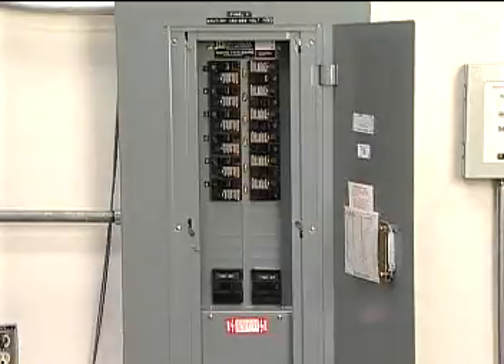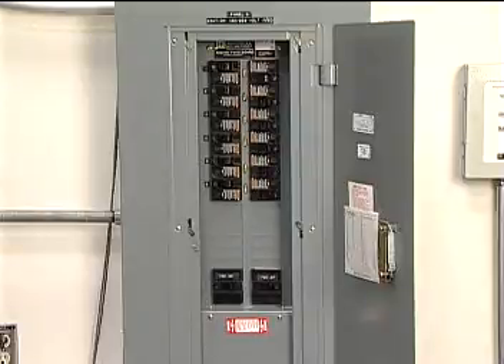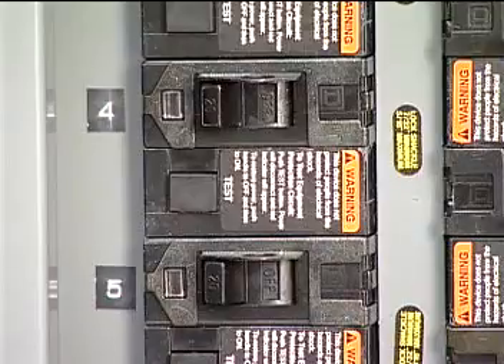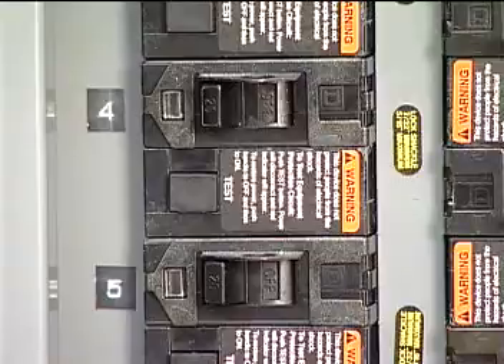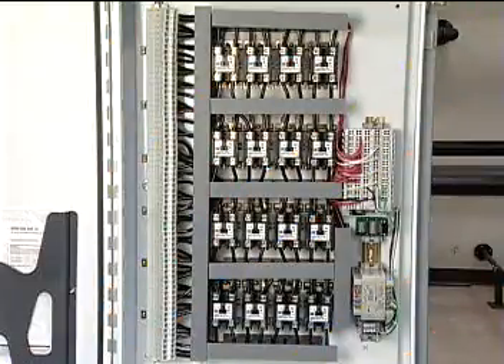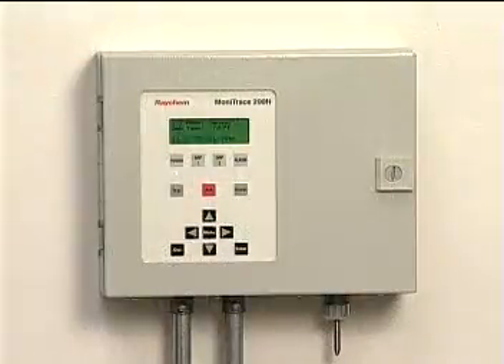Power is supplied to the heat tracing system via the distribution panel. This panel contains branch ground fault circuit breakers, which are sized individually for each circuit. In some cases, the panel also contains contactors and temperature controllers. Power is supplied to the panel by a transformer via the main breaker.